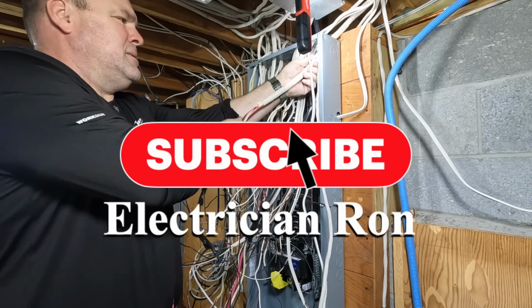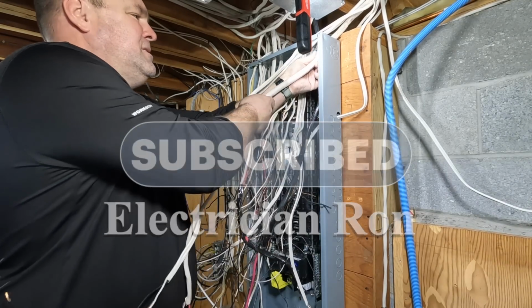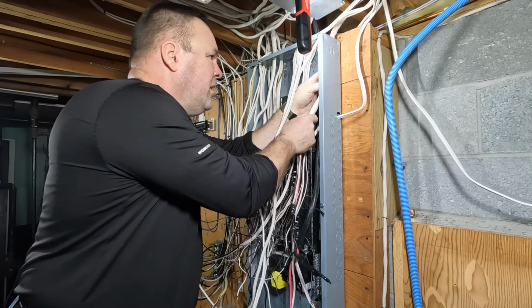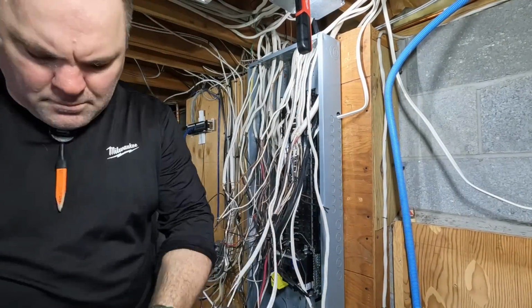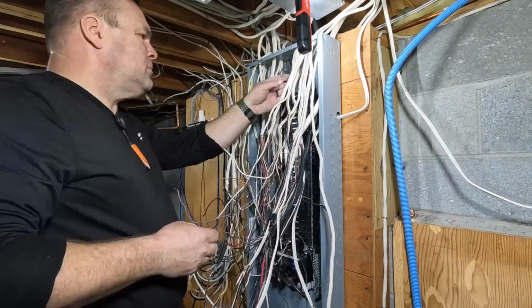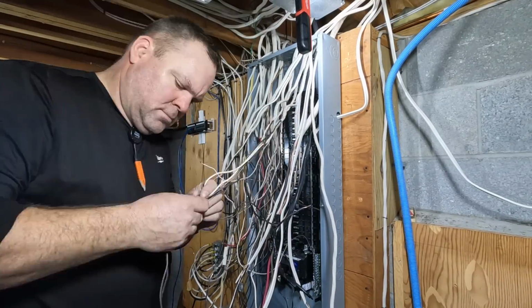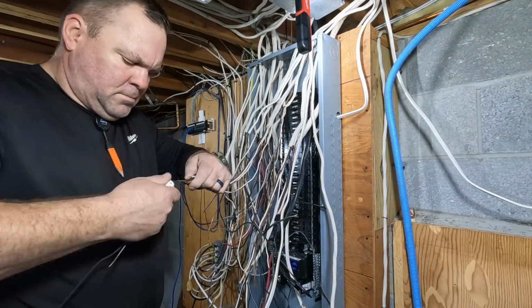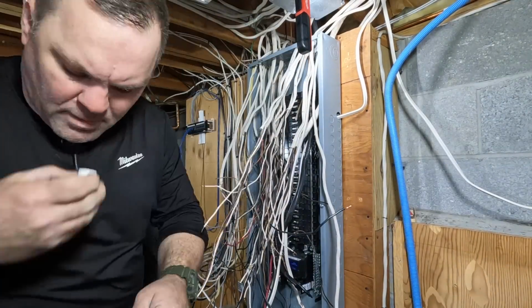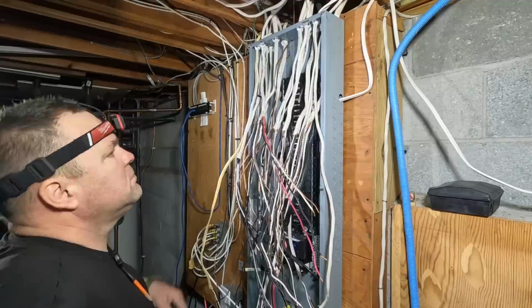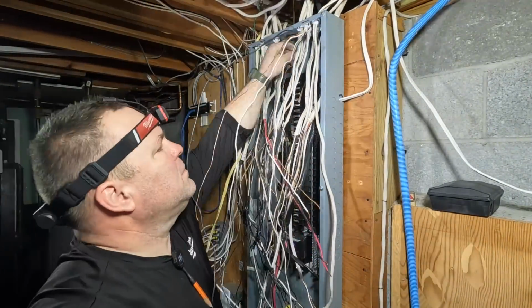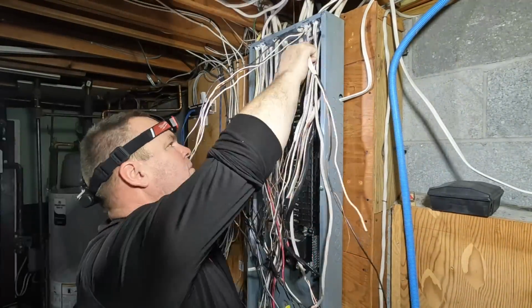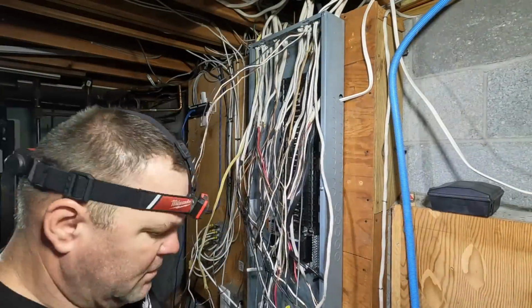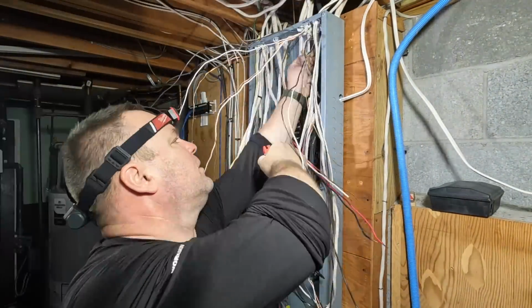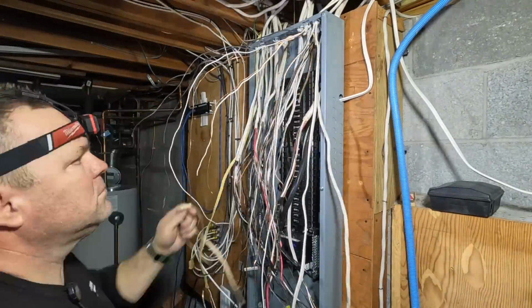There you go. That one's in. That's nice. What I have learned from installing these connectors is to slide them onto the cable and then push the cable into position with the connector. And then once the connector connects to the enclosure, now pull the wires back down to where you want them to land. We're going to eventually come back here, obviously now with the utility knife, and we're going to pull away all the sheathing. And this will go on for as long as I have to do this.